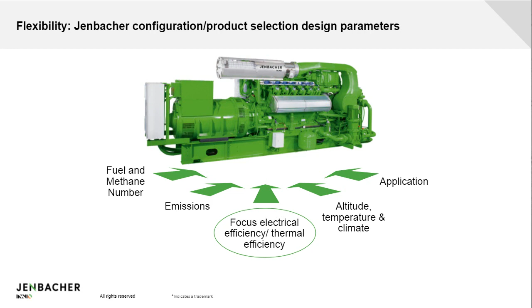Engines are not only rated for what they can produce at sea level; many factors affect performance. One is altitude — our engines perform very well up to 2,000 meters and almost do not derate. The higher the temperature, the more they start to derate, but our engines still perform very well up to 40 degrees Celsius (104 Fahrenheit). Humidity is also important, so every engine is custom designed for its specific location to produce the best result. Finally, the application matters too — whether it's for CHP (combined heat and power), generation only, biogas, greenhouses, etc.